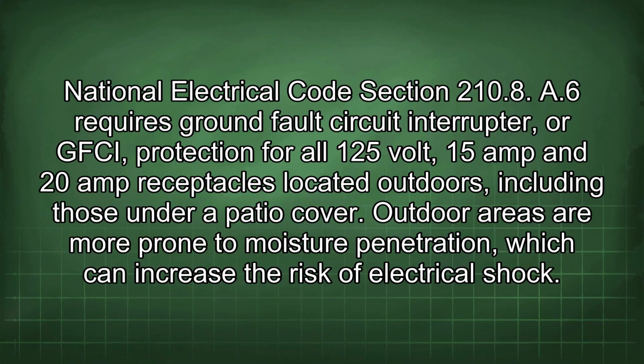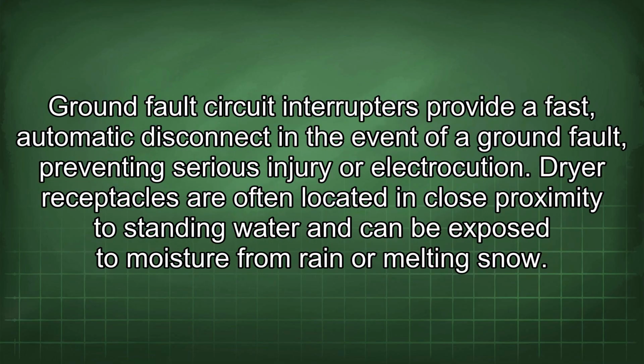National Electrical Code Section 210.8(A)(6) requires ground fault circuit interrupter, or GFCI, protection for all 125 volt, 15 amp and 20 amp receptacles located outdoors, including those under a patio cover. Outdoor areas are more prone to moisture penetration, which can increase the risk of electrical shock.